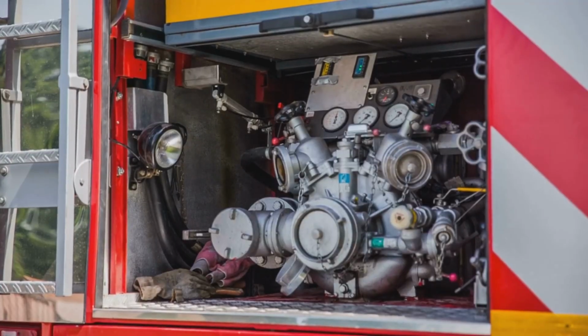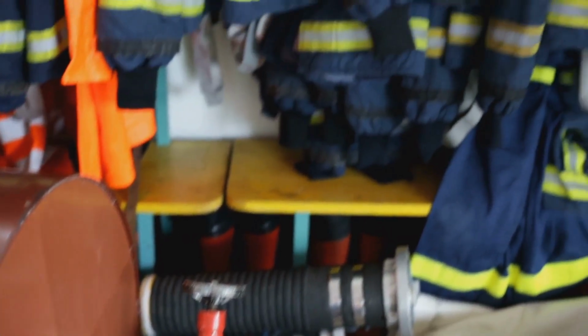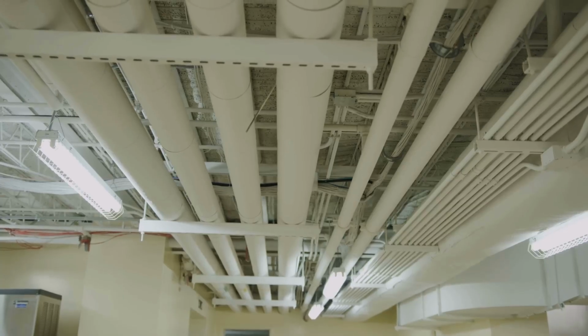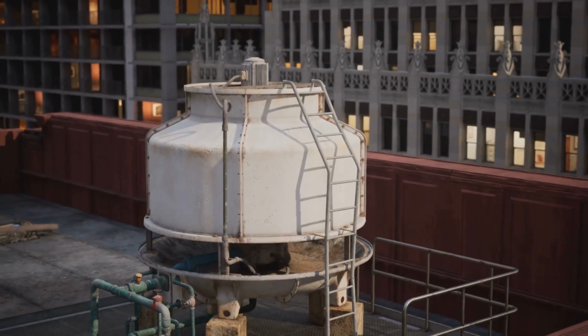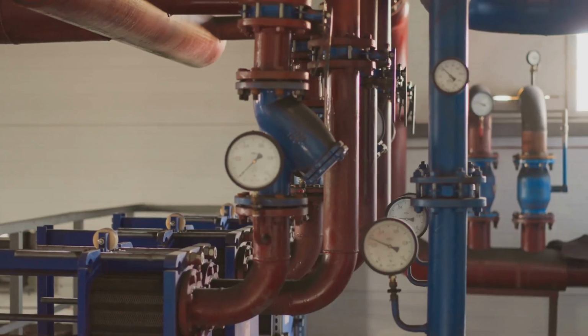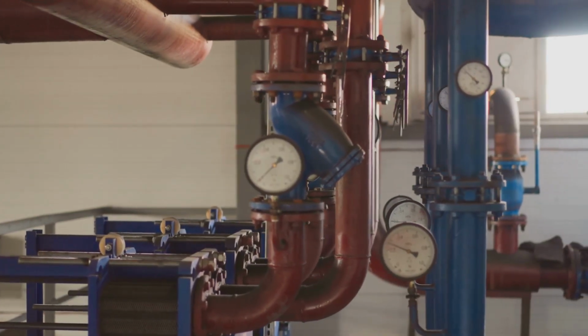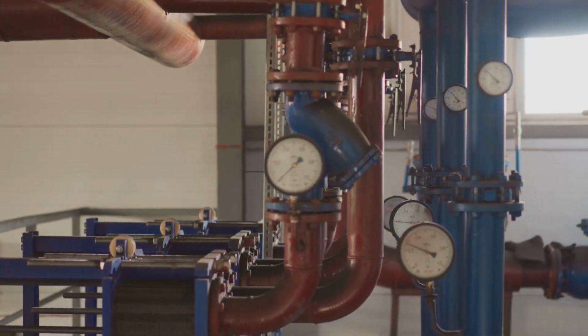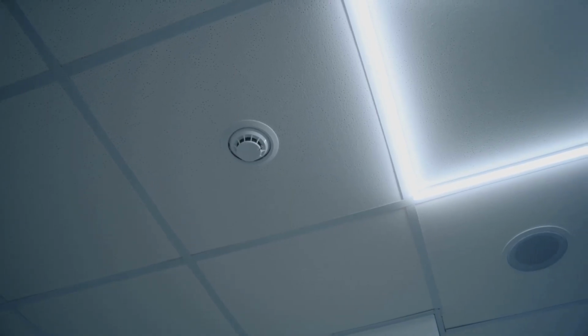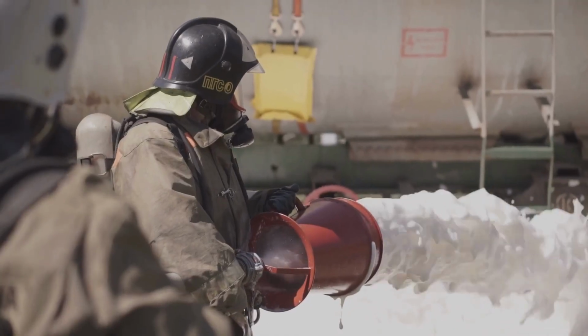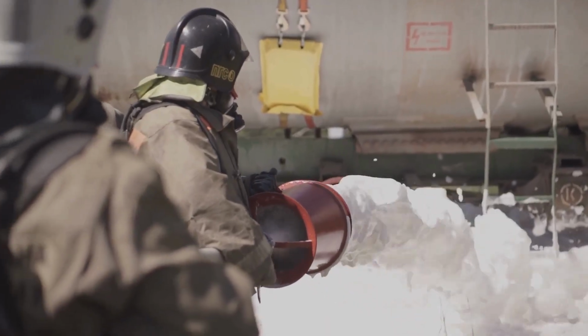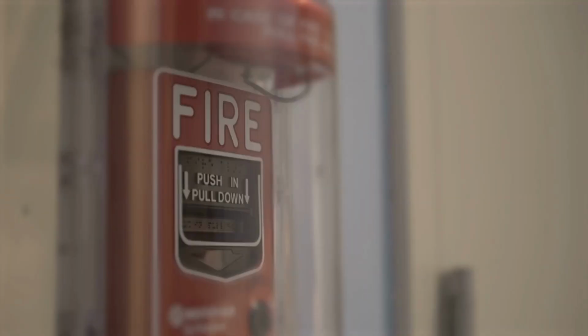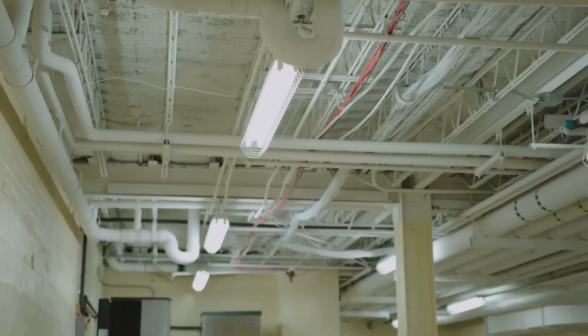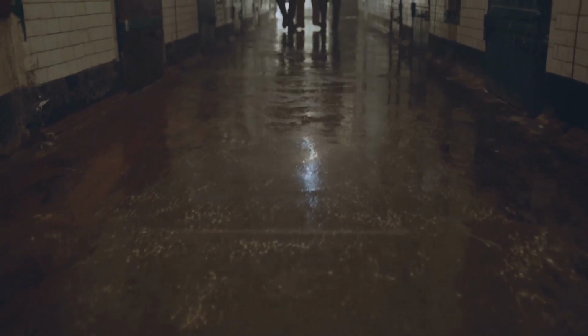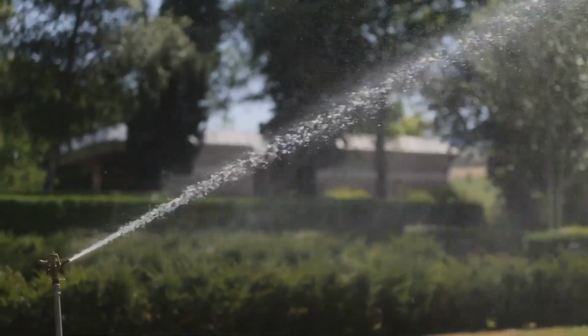This is where fire pumps come in. A fire pump increases water pressure to make sure it can reach every part of the building, especially upper floors. Some buildings also have dedicated water storage tanks. These tanks ensure there's a reliable supply, even if the main water system is disrupted. So when a sprinkler activates, it's not just releasing water, it's drawing from an entire system designed to deliver it quickly and consistently. And all of this happens automatically. No human input required. That's what makes the system so powerful. It doesn't wait for firefighters to arrive, it starts working immediately. And that early response makes a huge difference.